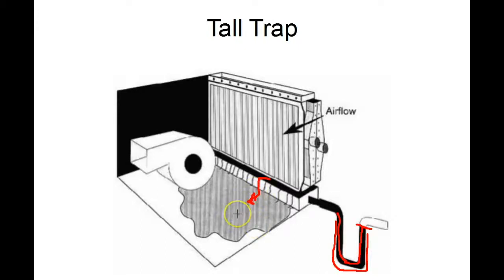This is a big issue because first of all, this creates a huge amount of microbial growth and if it's in an attic and everything isn't exactly perfect to prevent this from happening, it's going to drip through the ceiling. I have seen in South Carolina where portions of the ceiling have just caved in and fallen in because of all the water saturation that's dripped out of a situation like this.